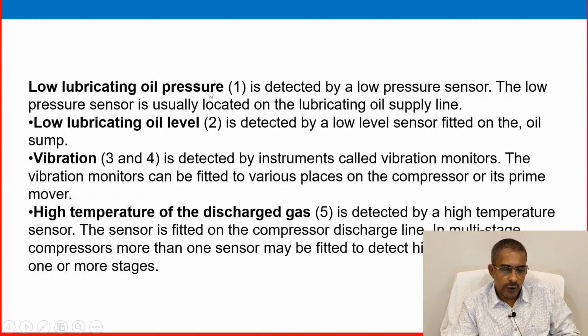Low lubricating oil pressure is detected by a low pressure sensor. The low pressure sensor is usually located on the lubricating oil supply line. Low lubricating oil level is detected by a low level sensor fitted to the oil sump. Vibration is detected, already we have discussed that one. Vibration is detected by an instrument called a vibration monitor. The vibration monitors can be fitted at various places on a compressor or its prime mover.